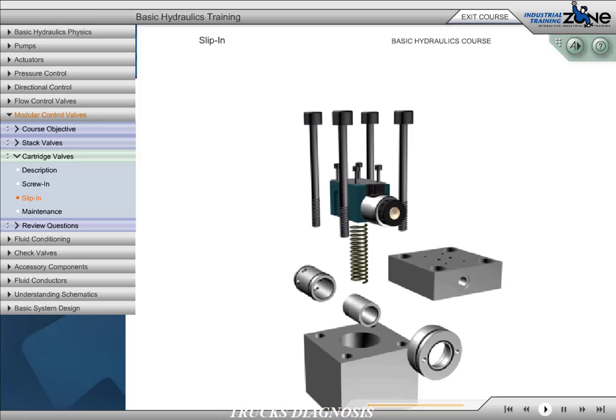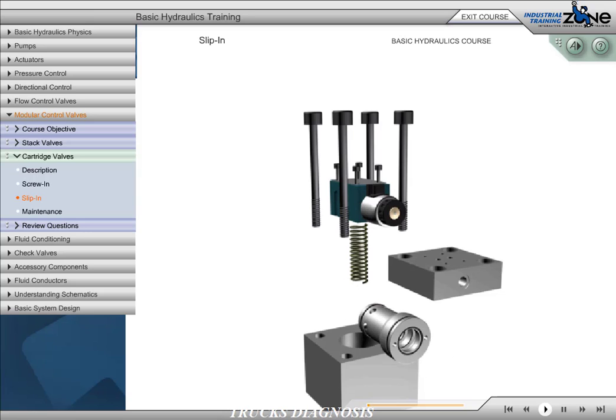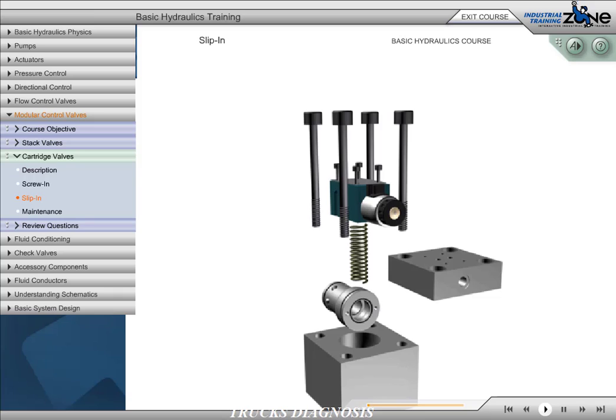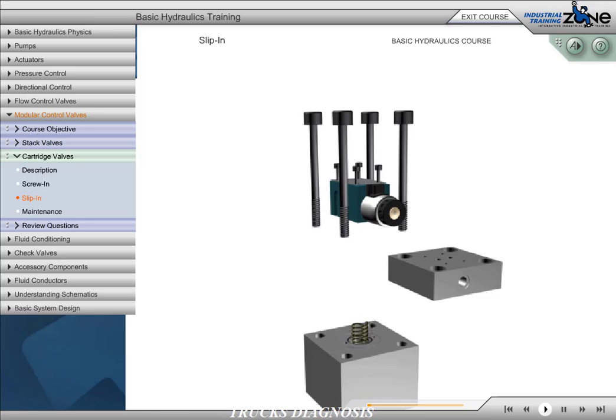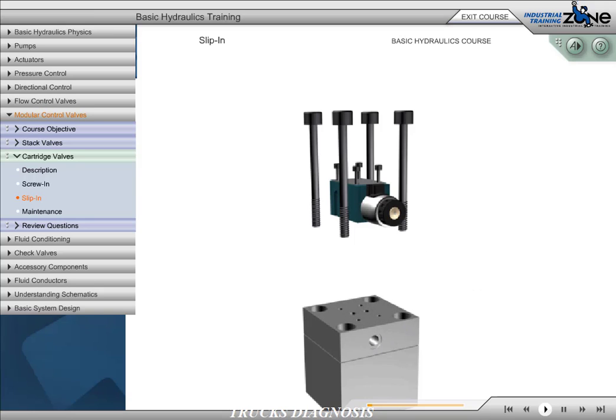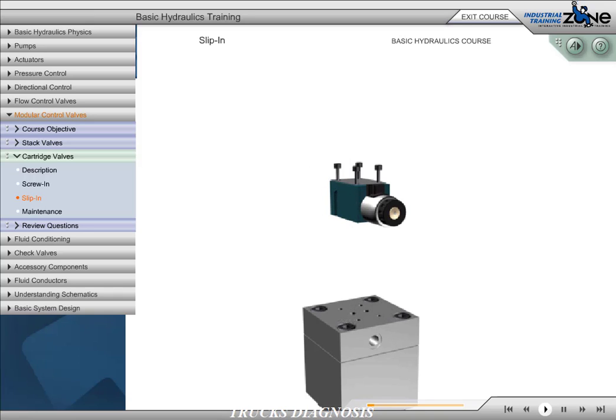Slip-in cartridge valves use an insert consisting of a poppet, spring, seals, and a sleeve, which slips into a cavity machined into a manifold block. A cover assembly bolted to the manifold block secures the insert in the manifold. The cover assembly usually contains one or more internal flow paths which allow the cartridge valve to interact with another valve in the manifold to create a specific function within the manifold.